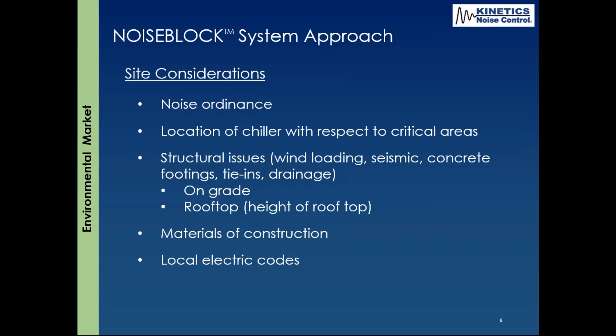Then we look at materials of construction—is it a coastal application? We need different materials for coastal environments, and do they want a powder coated finish? Also part of the code is the local electric code. In the end, some of these solutions have to be shoehorned in because we need a lot of noise control, and we may have to encroach on the clearances the air-cooled chiller manufacturer recommends. But we can't encroach on the electric code clearance between the equipment and a solid surface wall—that's important to account for.